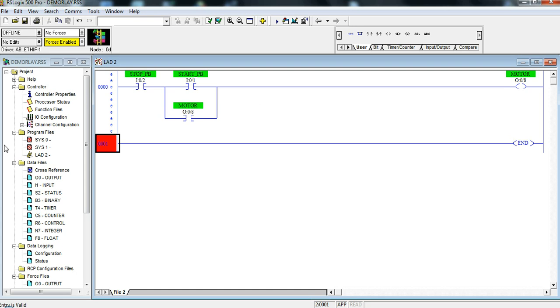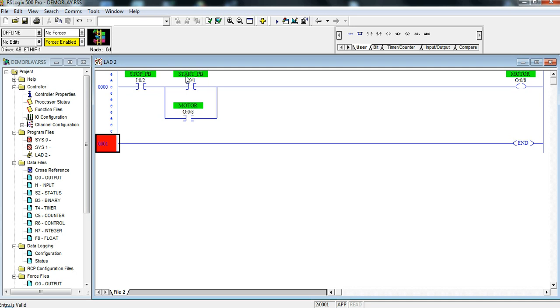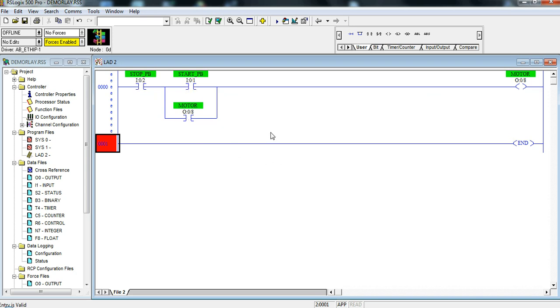Let's take a look at this here and think about it before we download. This stop push button since it's wired normally closed and this is an examine if closed instruction, I like to call it normal position instruction. In its normal position this will be high and we'll look at our start push button and its normal position will be low. In order for this logic to reach the motor we have to have both of these high or this high as well. So let's go ahead and download this right now.